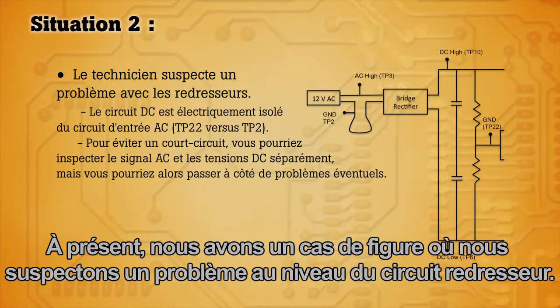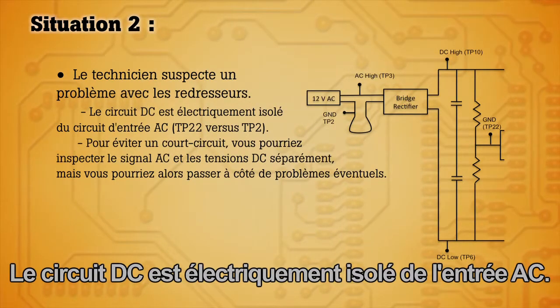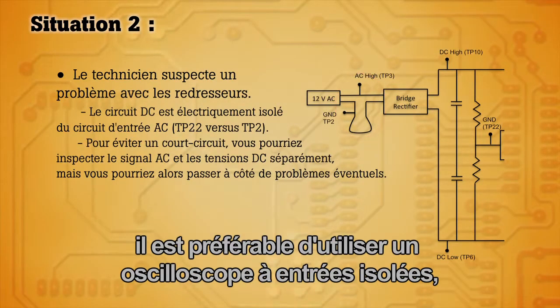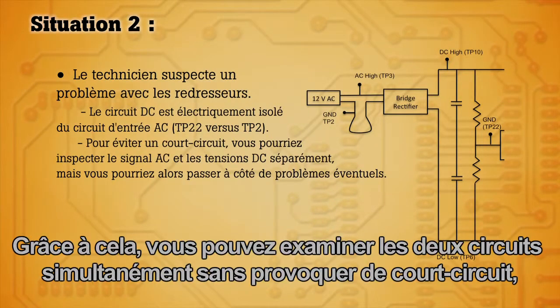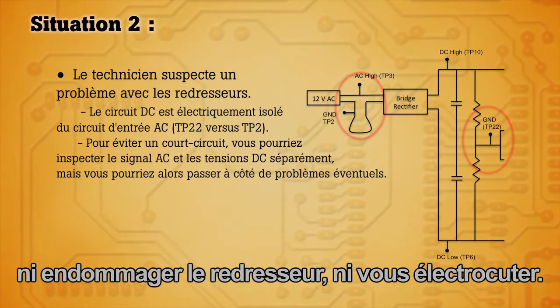Here we have a scenario where we suspect that there is a problem with the rectifier circuit. The DC circuit is electrically isolated from the AC input. In order to troubleshoot that circuit correctly, it is best to use an isolated input oscilloscope like the Scope Meter 190 series. This will allow you to look at both circuits simultaneously without causing a short circuit and damaging the rectifier or yourself.